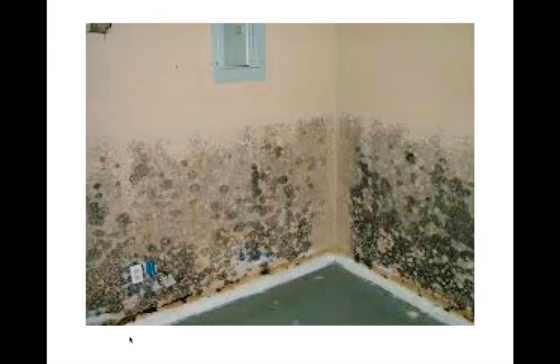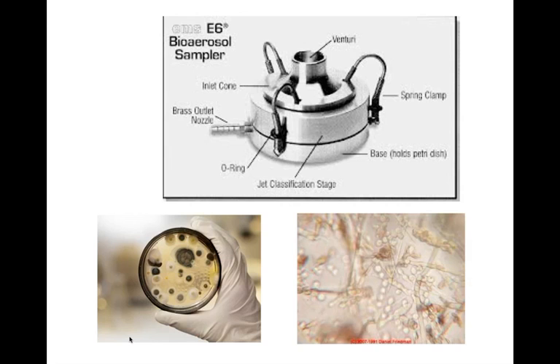Recommendations vary based on the amount of mold: two or three square feet is basically a maintenance issue requiring basic precautions; more is required over 10 square feet, more still over 30 square feet. It's based on how much mold you have, not what kind, because there's not a lot of agreement about which molds are really bad. If you do want to test for mold, one device is the EMS E6 Bioaerosol Sampler — you put a Petri dish in, pull air through to impact particles onto the dish, incubate it, and then identify and count the mold types under a microscope.